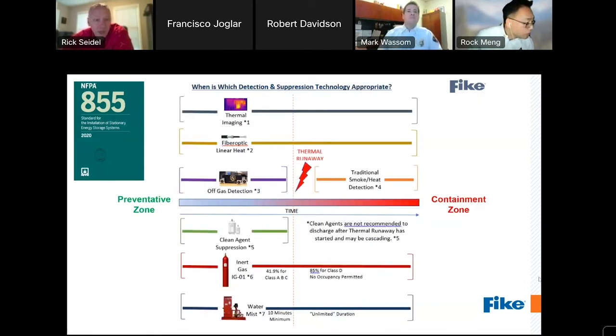And just to graphically depict which detection and suppression technology is most appropriate or available, and where that puts you in the time frame as far as preventative versus containment zone in reference to thermal runaway, this slide here helps to show you. The important thing is to know, whichever selection you make, where it puts you as far as your level of protection, and understand and be willing to accept that level of commitment. Next, please. I think that's it.